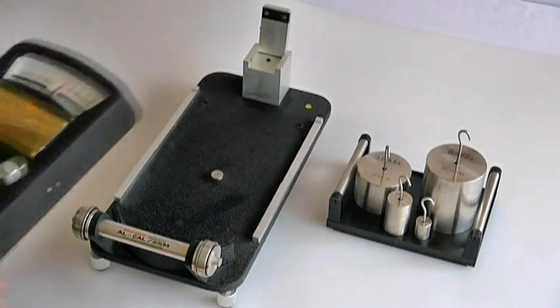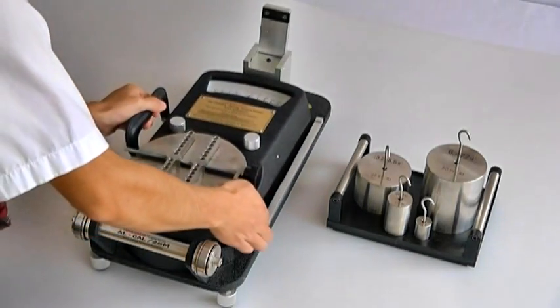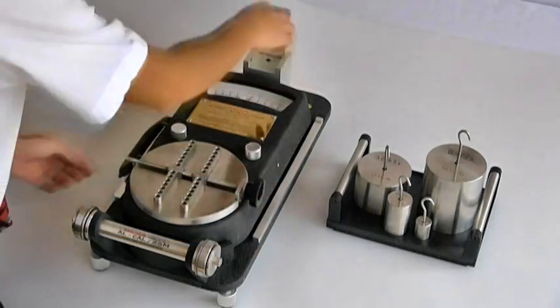The platform on which the torque tester sits provides the tools for calibration. A variety of precision weights are available.